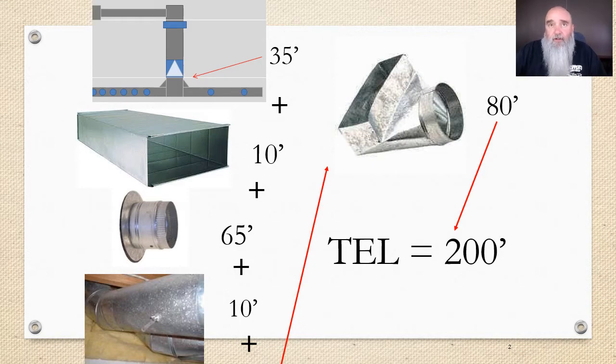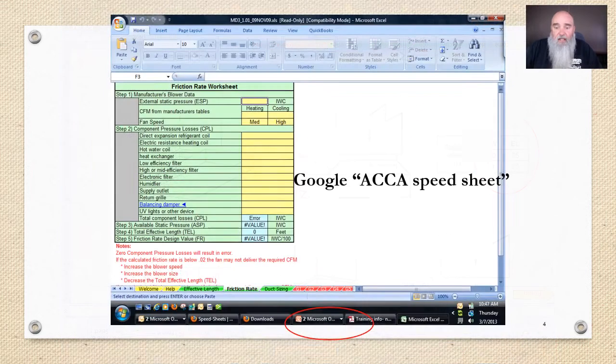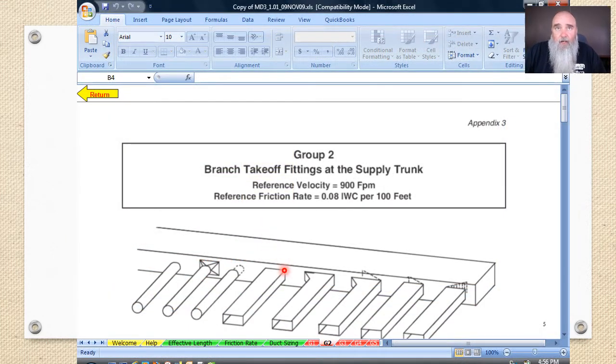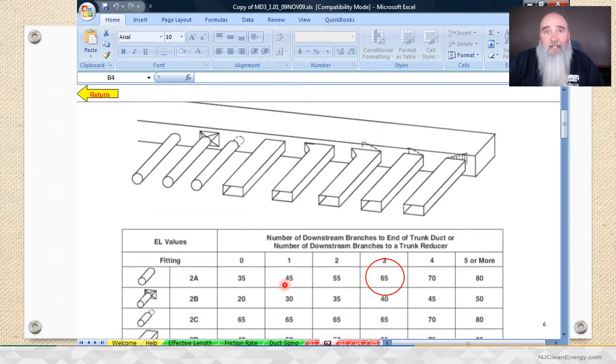We have some charts that you can find on the Manual D speed sheet or look up in the book, and it'll tell us what these lengths are. This is the Group 2 diagram, and below it'll show us what those ELs are.